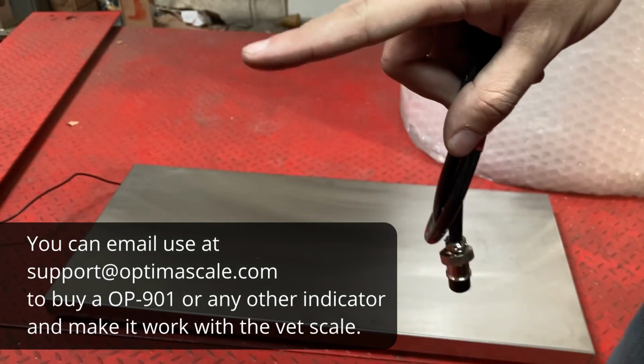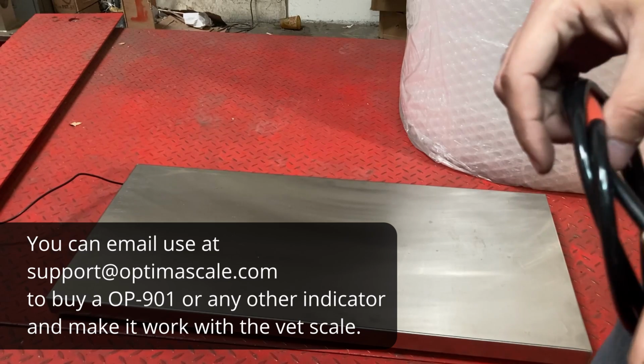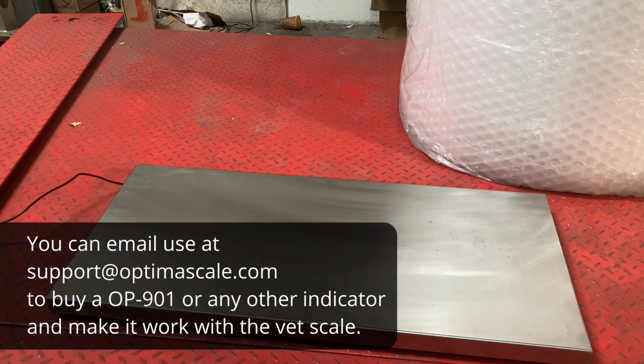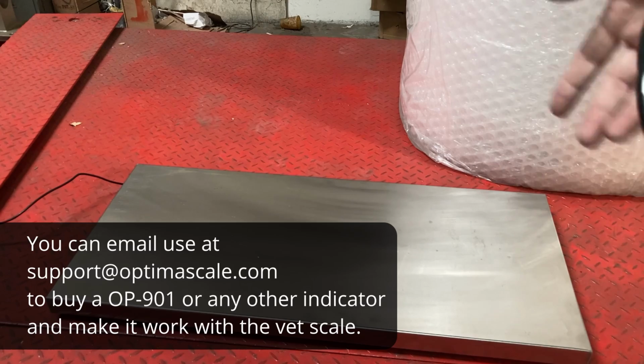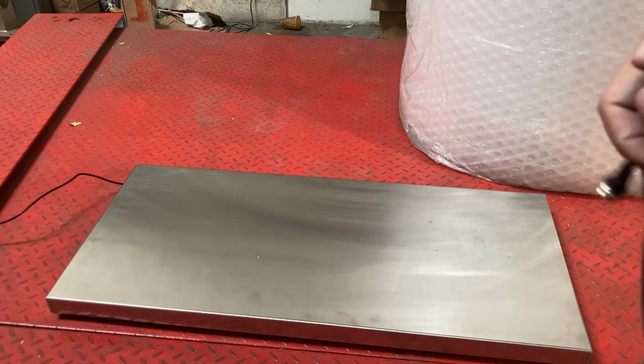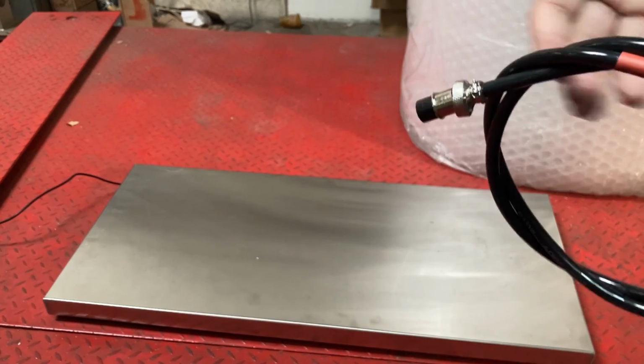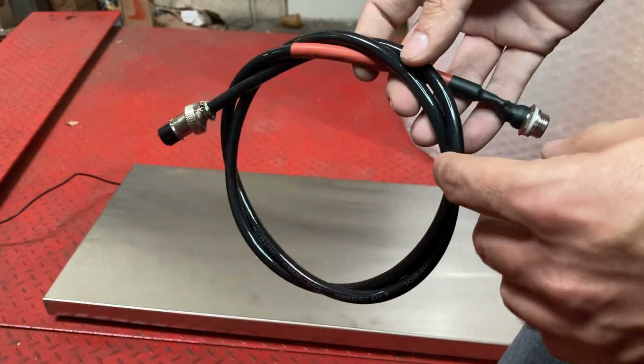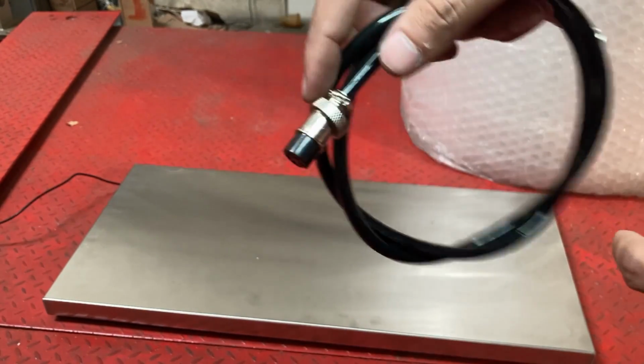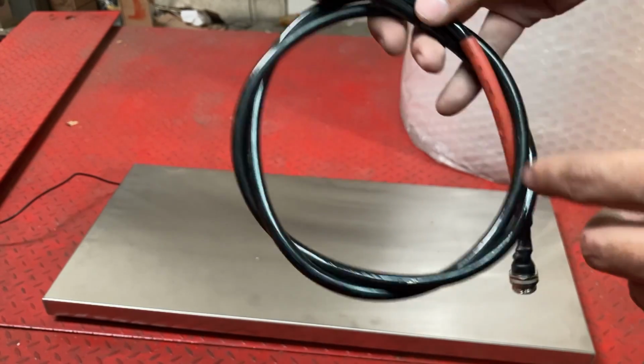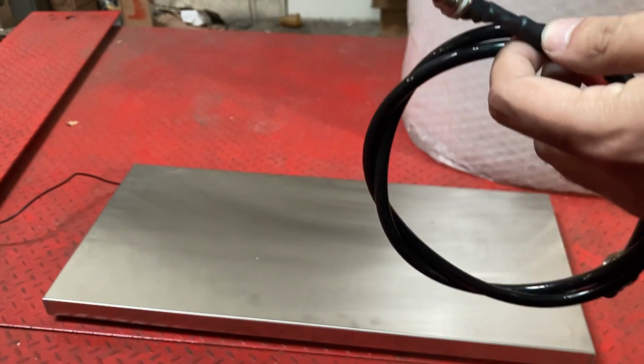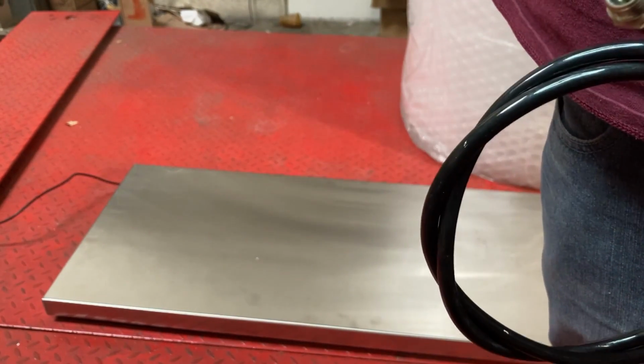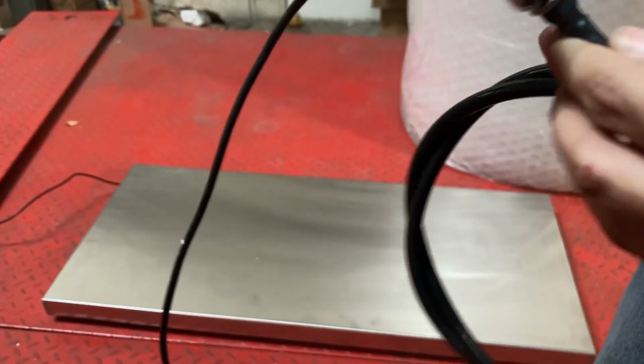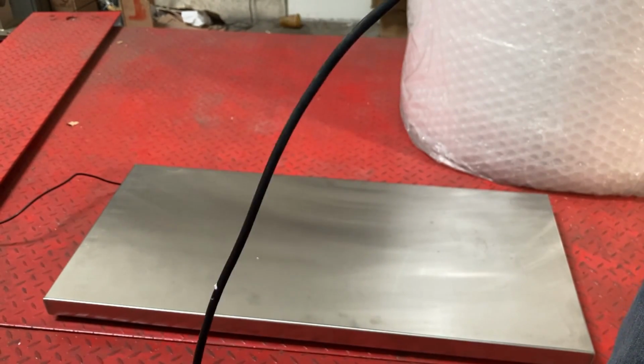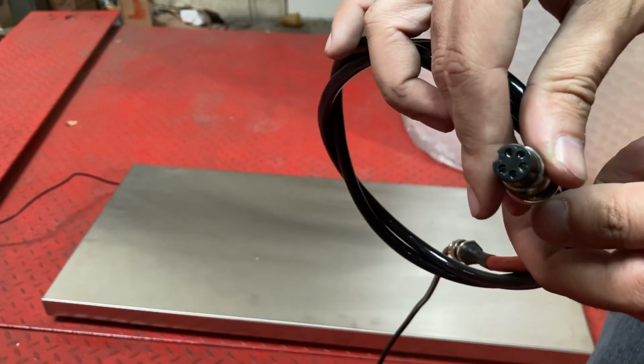Well, instead of using the same 902 that has this issue, you can start using a 901 indicator. With the 901, I've seen those last 10 years without a problem. They don't have the same kind of failure rate that 902s have, but it costs maybe $20 or $30 more. I think it's worth the upgrade from a 902 to a 901 if you have an indicator that failed. Because with this cable, you just plug it into the 4-pin connector, the 4-pin from the scale, into this cable, and then you can plug it into a 901, which I'll show you right now.